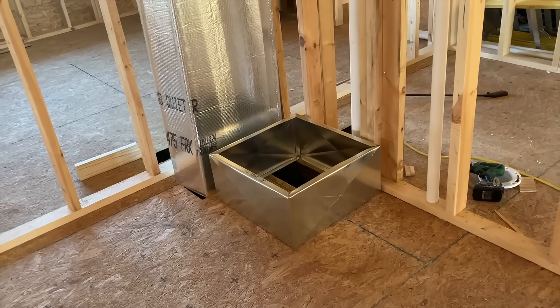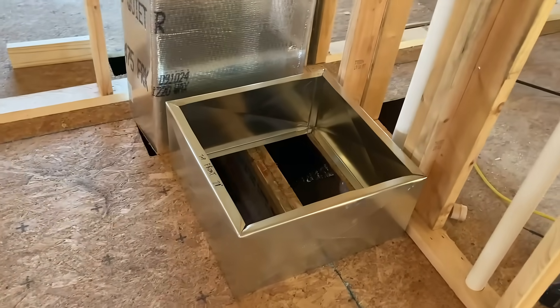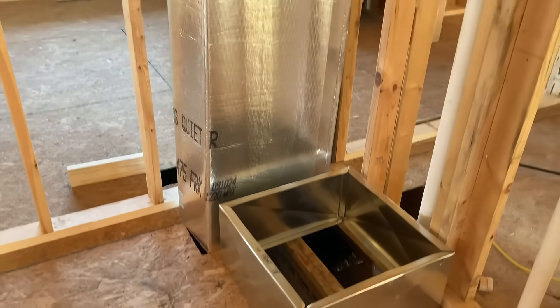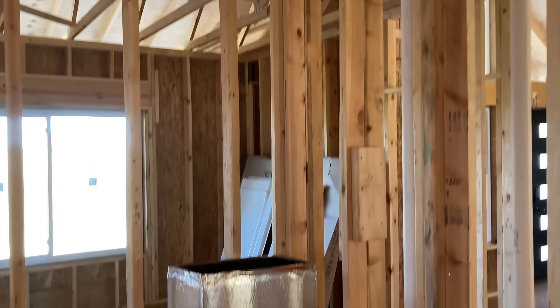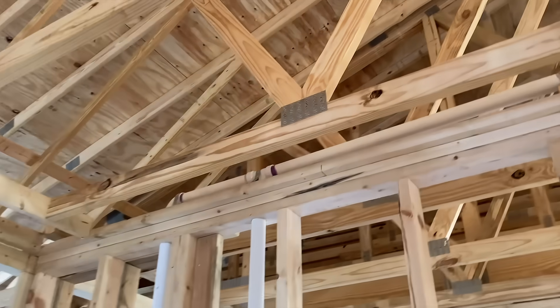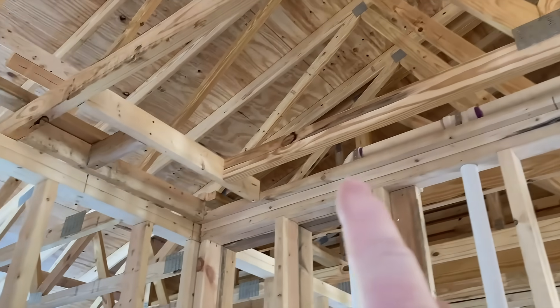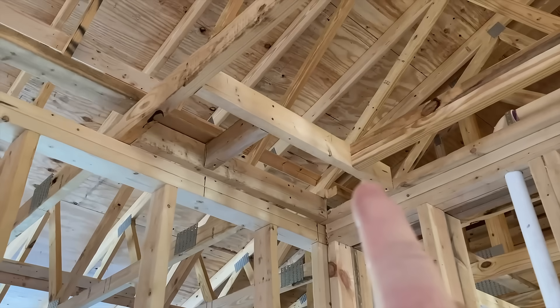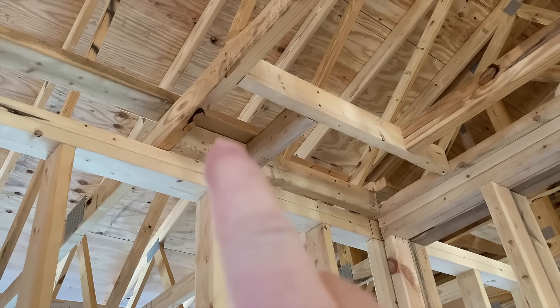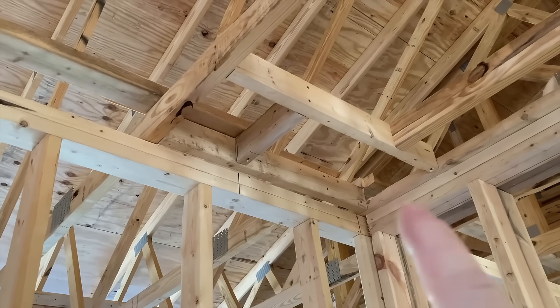This is what I saw on the ground — the placement that we discussed, and ductwork going down through the floor. We also discussed that some ductwork will have to go up through the ceiling. The first thing I see is this roof truss here, and he just cut it. You can barely see it, but there's also this 2x4 there — that's engineered structural bracing, and he's cut this also.